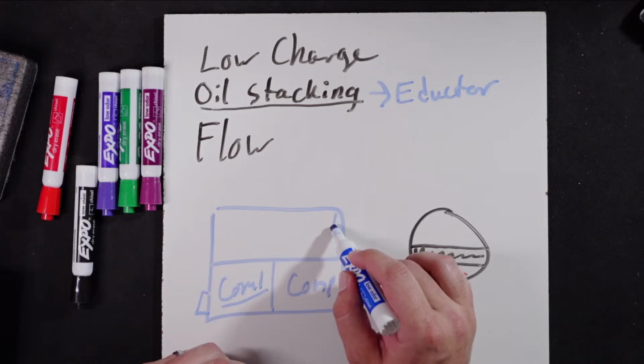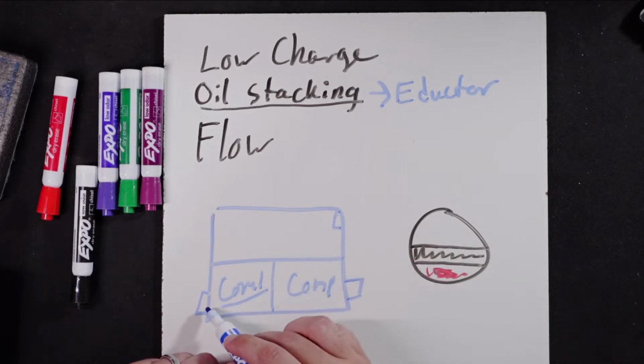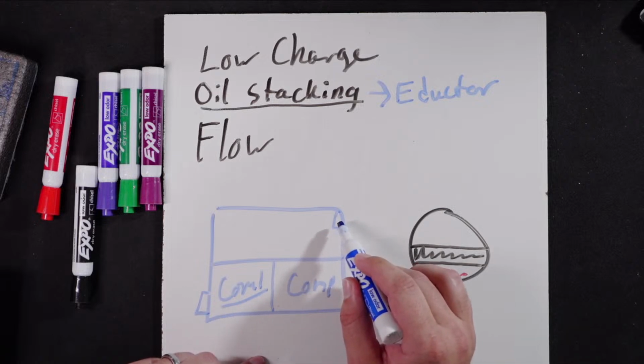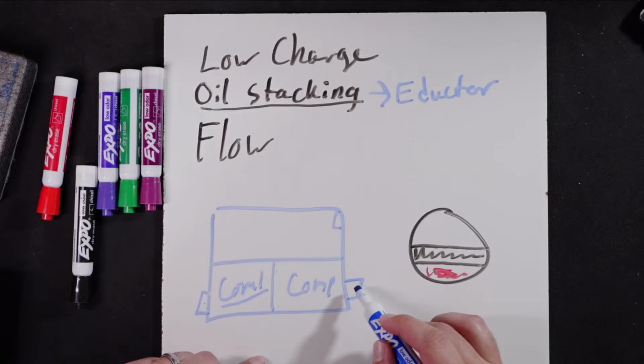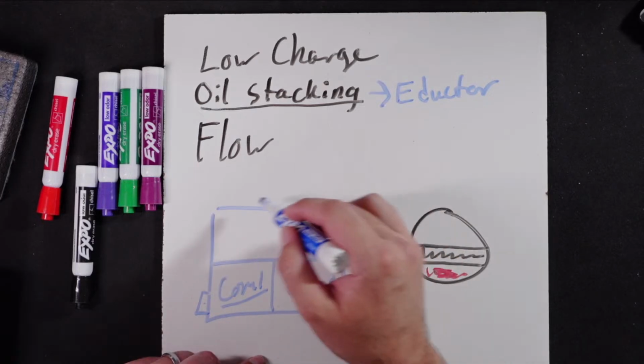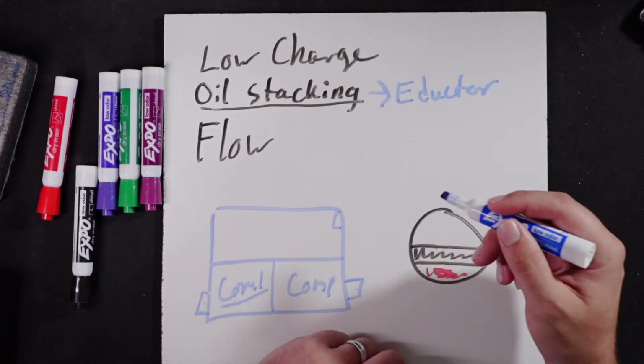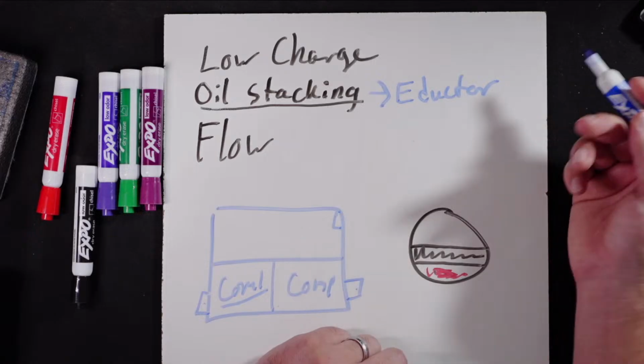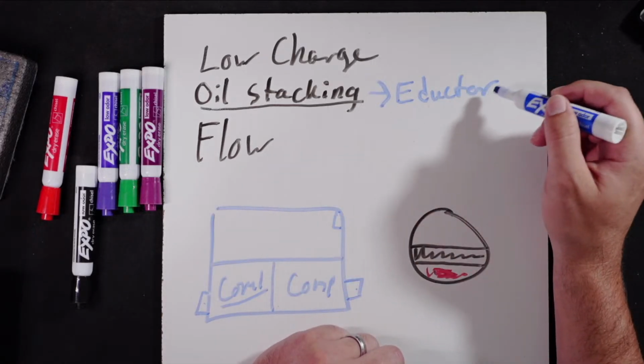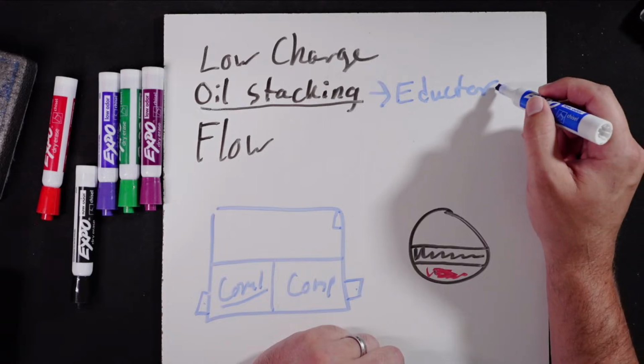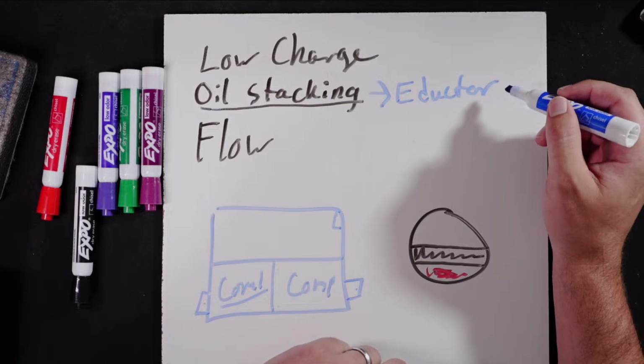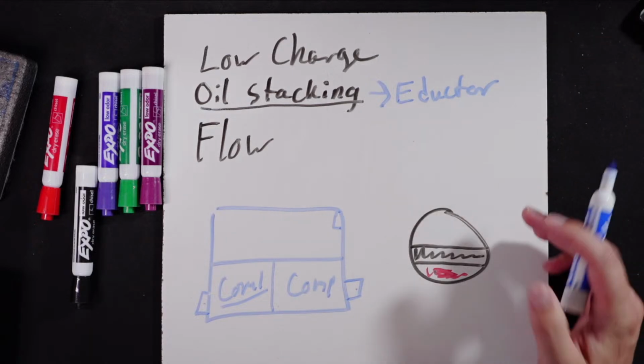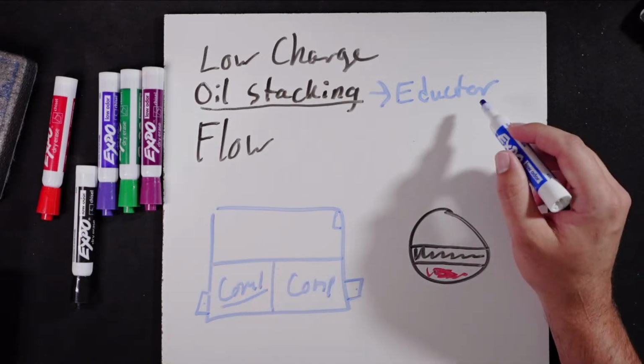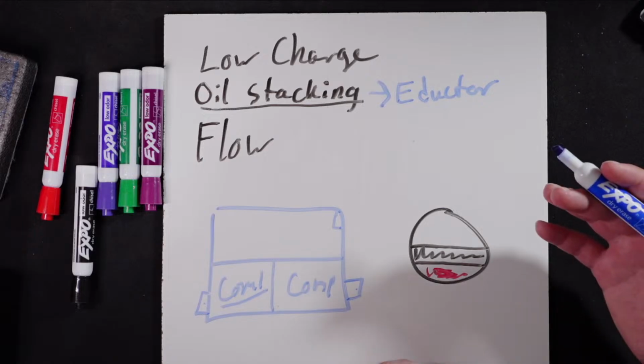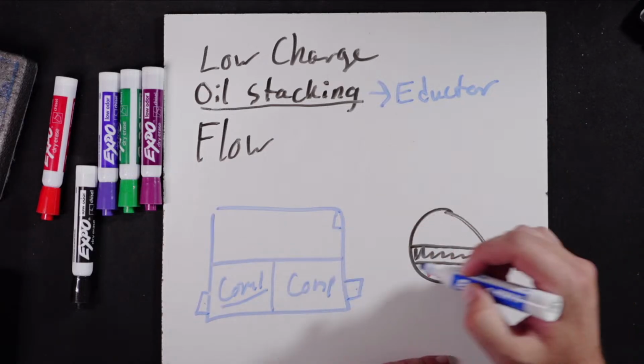So you still have the contactors up here in the corner, but these contactors are basically hard contacts to open power to the condenser fan drives, and then the condenser fan drives are what's actually feeding the fan decks themselves. So again, if you're having a head pressure issue, that's going to influence the eductors and your ability to return oil. So more than likely, though, I would really want to blame the eductor, drier, or an overcharge of oil. If for some reason somebody added an excessive amount of oil to the system, that's going to cause similar stacking issues because we have more oil flowing through the circuit than we were actually designed to be able to recover at a given time.